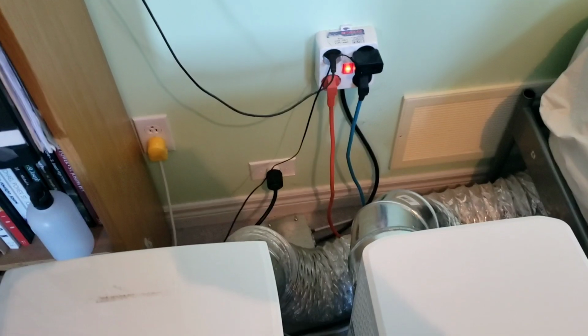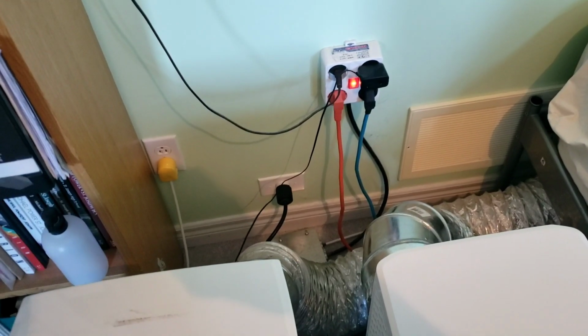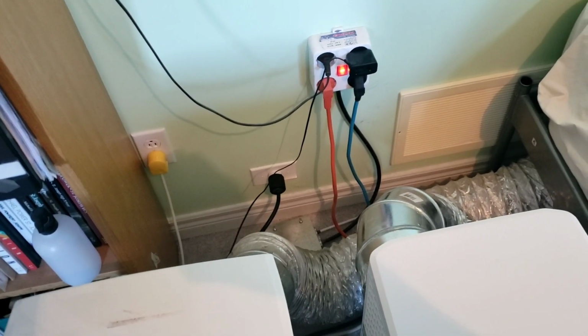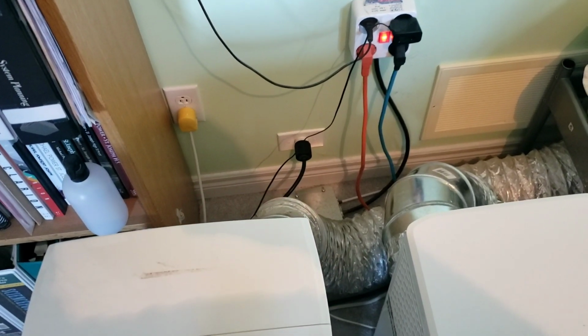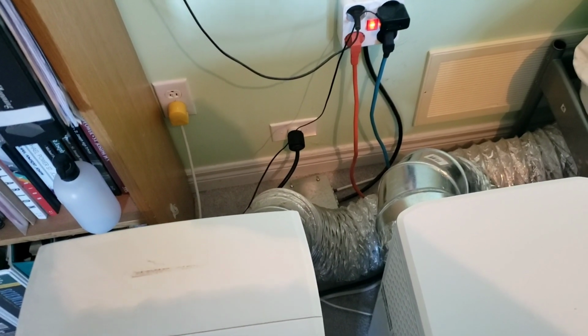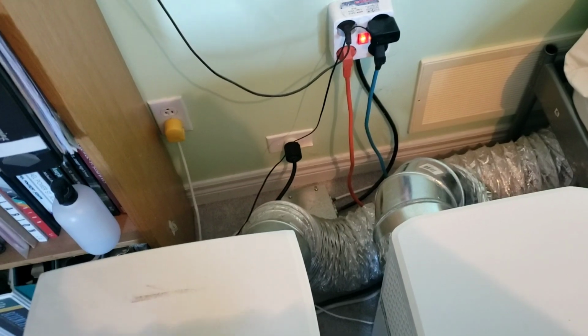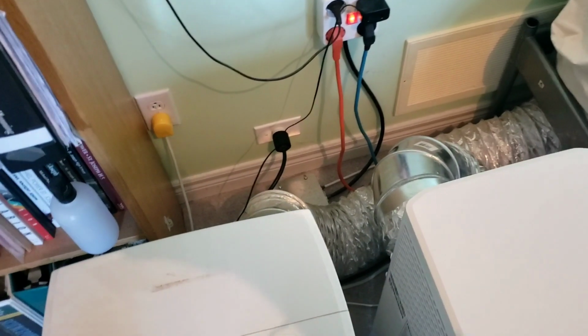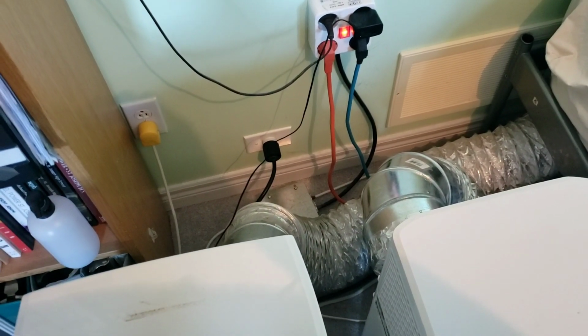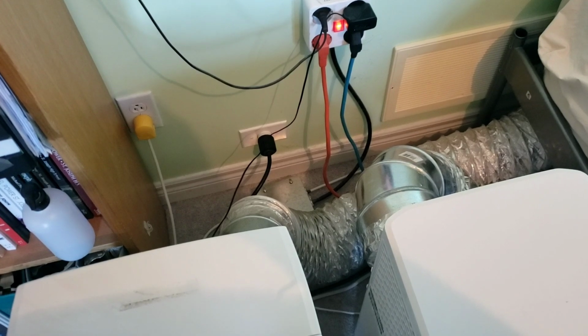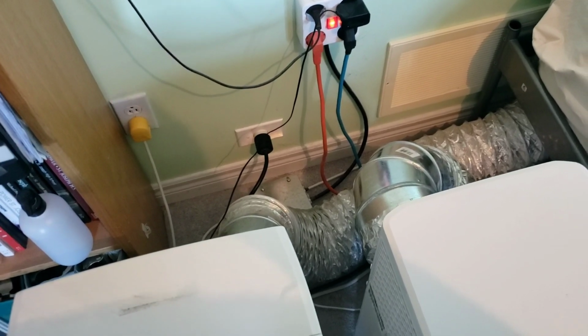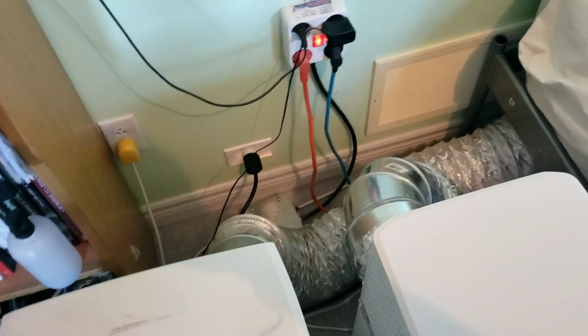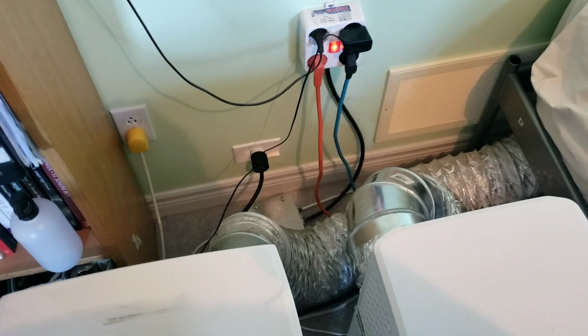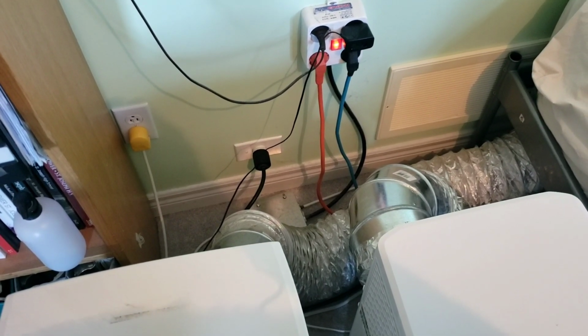Now with the electrical, the trick is to have the voltage converted from 120 volts that was feeding that receptacle, which comes straight from the panel into 240. So you just put a double breaker here in North America, that's all you gotta do. Now these air conditioners are on 120, and you're wondering, did I put them in series? No, I did not put them in series. You can't. So what I did was install two transformer units for them.